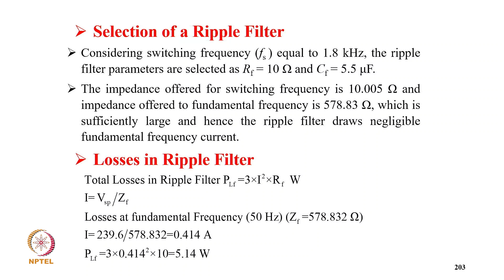Losses in the ripple filter: total loss in the ripple filter PLF equals 3 into I square RF, where I is typically VSP upon ZF. The losses at fundamental frequency of 50 Hz, ZF equal to 578.83 ohm, and I equal to, putting a value, 239 divided by 578.83, it comes 0.414 ampere, and PLF equal to 3 into I square into 10, that comes 5.14 watt.